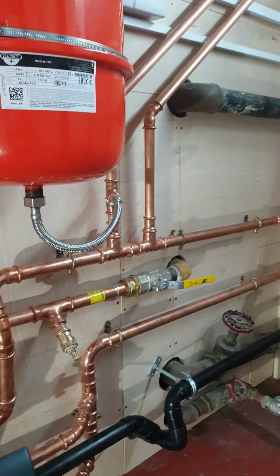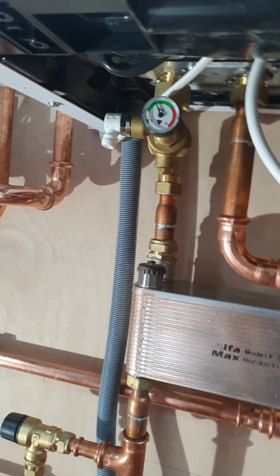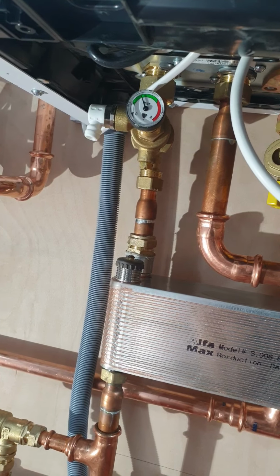So we've put the filling valves in over here on the returns from the cylinder, and it doesn't actually matter if they're on the flows or the returns, but they're on the loops from the cylinders. And because the diverter valve in the boiler is now on the flow on the 200 instead of on the return, that's going to give us water coming in through the return on the hot water when we top up, which allows us to blow all the air out of the heat exchanger through the little drain cock on this side.